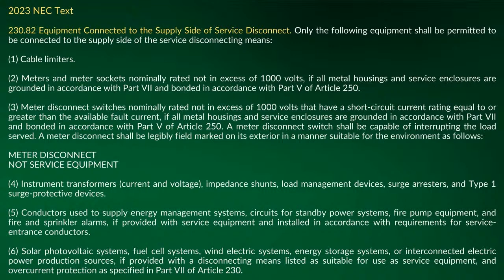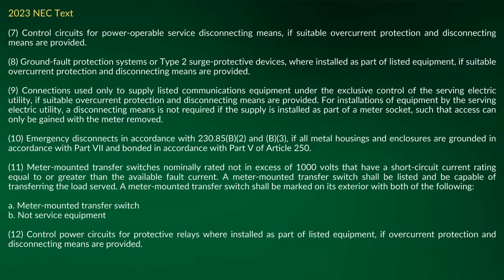Now, what this comes down to is when you look at 230.82, we talk about equipment connected on the supply side of the service disconnect. Okay, that's what we want to discuss here. If you're on the supply side, all of these items here, I'm not going to go through every one of these, but this is what they're talking about can connect on that supply side. And as you'll see, it goes to where you got 12 different things here you can look at. Okay. Now, the one I'm going to point out is number 10 here, and it says emergency disconnects in accordance with 230.85 B2 and B3 if all metal housings and enclosures are grounded in accordance with Part 7 and bonded in accordance with Part 5 of Article 250. I'm going to discuss that here in just a second.